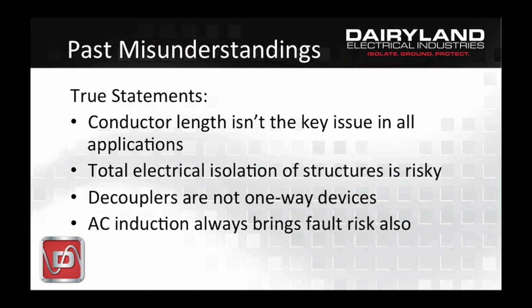Further topics. Sometimes conductor length isn't the key issue for all applications. One can think of this as being a practice to be followed in all situations, but there are some applications, such as a code-covered grounding conductor, that just can't be shortened if it's running from a panel to an electrical device. Next, electrical isolation of structures can be risky if there's no overvoltage protection provided. So sometimes structures are left mechanically isolated one from another using insulated joints, but users have provided no overvoltage protection, and they just somehow think that magically this structure will remain isolated forever from the other structure. However, then it means it can rise in voltage to any level. There's no means of protection.